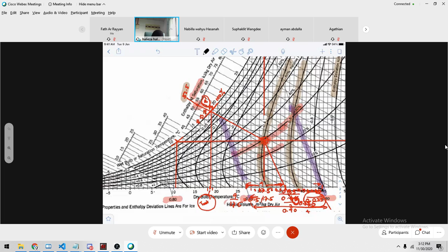So the saturation enthalpy, the enthalpy equals 52.5 minus 0.4. Now I know why I could not write just now. It should be 52.1, and the unit is kilojoules per kilogram dry air. Look at this unit, kilogram dry air. That is your enthalpy.